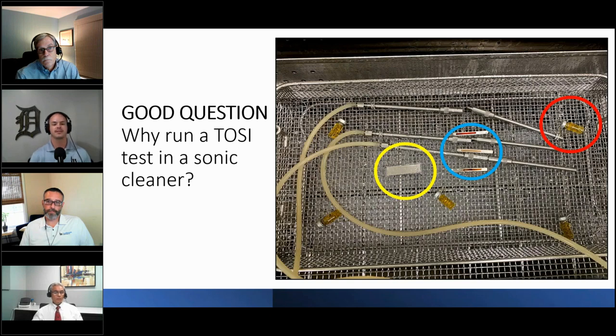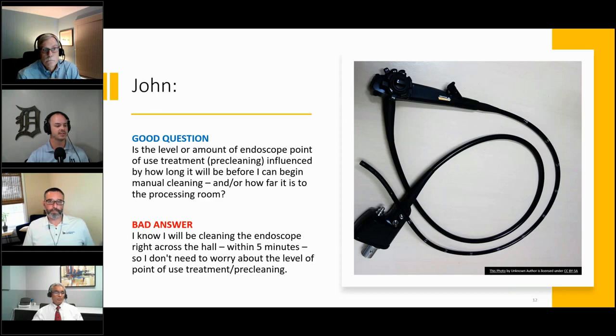So yes, the cavitation was there. Yes, the TOSI or the external soil was being removed, which is great. But again, you go back to our good answer, which is running each test that makes sense for the function that we want to do, right? We want to run all the necessary tests of our ultrasonic. And in this particular case, we had external soil removal pass, we had a cavitation of ultrasonic energy test pass, but we did not pass that lumen or internal soil removal test, and therefore we were able to find an answer to the problem and solve it. So that is why we suggest that the best answer, again, is to run all necessary tests for the function of your ultrasonic. And again, that goes back to any washer or even cart washer, just like Seth had talked about before. And I think we can move on to the next question, which is going to be for John.